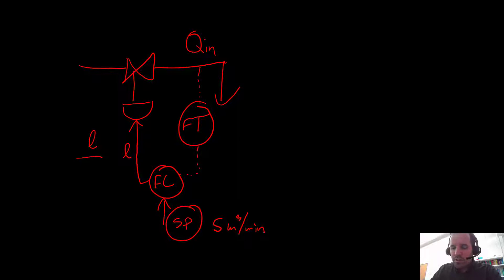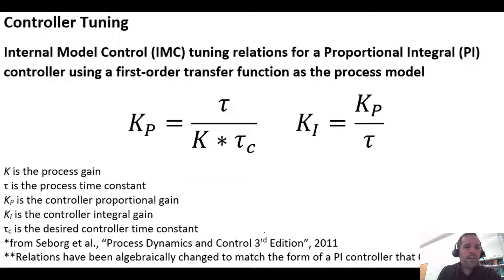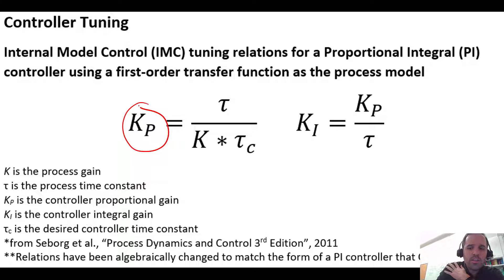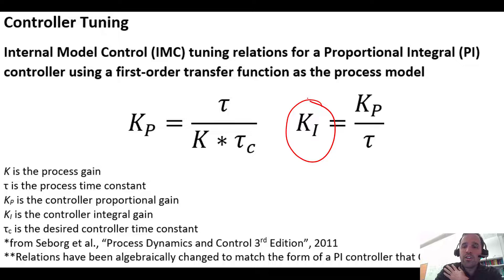There is a whole lot of information on control theory, but we're going to use some very simple tuning — specifically something called Internal Model Control or IMC tuning relations. We're going to use the proportional-integral algorithm; we will not use the derivative, to keep this fairly simple. Our controller has certain parameters we need to define: namely Kp, the controller proportional gain, and Ki, the controller integral gain.